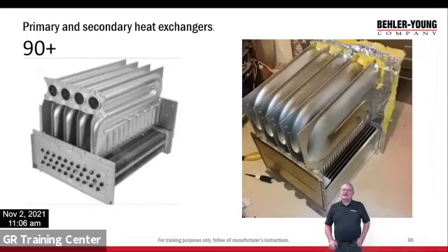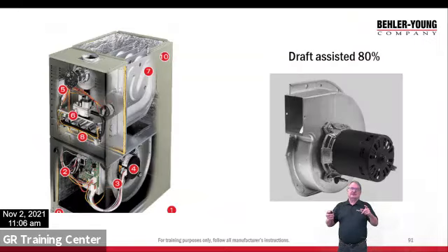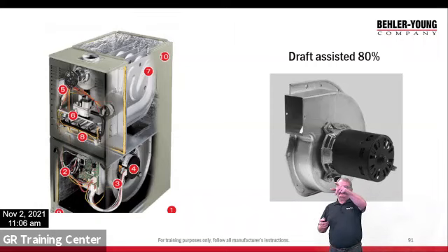But now underneath it, I have a second heat exchanger, or a secondary heat exchanger. Because back in the first 80% furnace, with this, I'd go through my primary heat exchanger over there. 300-degree flue gas would go through this vent motor up the chimney.